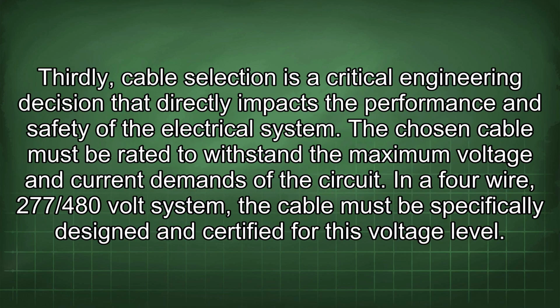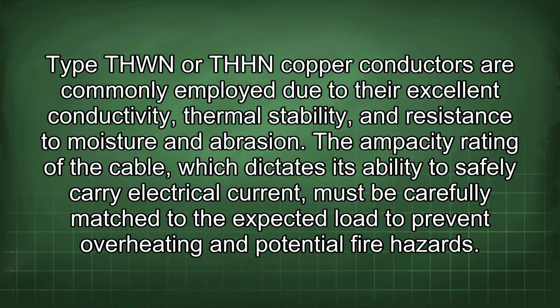Thirdly, cable selection is a critical engineering decision that directly impacts the performance and safety of the electrical system. The chosen cable must be rated to withstand the maximum voltage and current demands of the circuit. In a 4-wire 277/480 volt system, the cable must be specifically designed and certified for this voltage level. Type THWN or THHN copper conductors are commonly employed due to their excellent conductivity, thermal stability, and resistance to moisture and abrasion. The ampacity rating of the cable, which dictates its ability to safely carry electrical current, must be carefully matched to the expected load to prevent overheating and potential fire hazards.